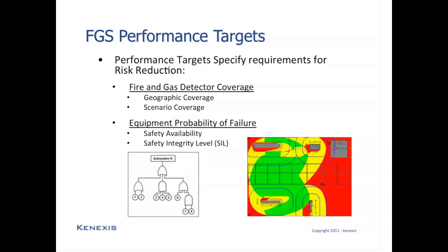84.00.07 technical report defines two types of coverage that you may wish to calculate. Those two coverage types are geographic coverage and scenario coverage. Geographic coverage essentially looks at a fire detector array or a gas detector array, and for that specific set of equipment and a given elevation of interest, will calculate what fraction of the floor space, or what fraction of that elevation of interest, that detector array can see. So if a fire were to occur in a specific location, would that detector array be able to see it?